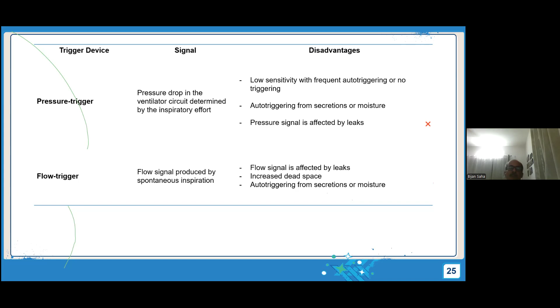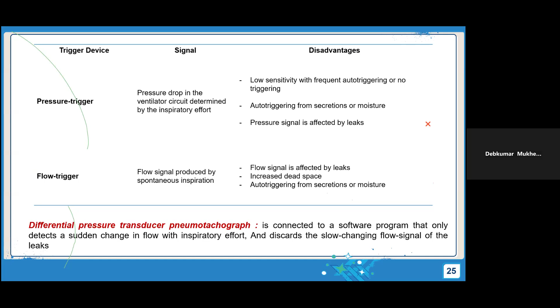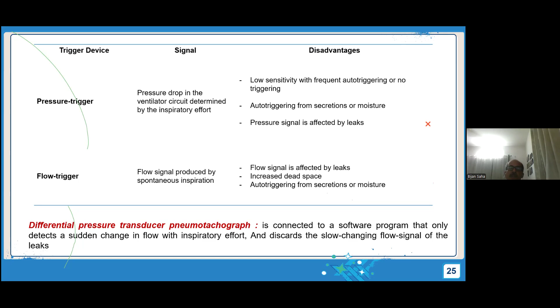So there is another flow sensor called the pneumotachograph. This is also a flow sensor, but it is not a hot-wire anemometer. Because of the change in the flow, there is some change in the pressure. That change in the pressure will be detected by the machine, and the machine will then deliver a breath. And the ventilator discards the slow-changing flow signal of the leak. Some ventilators use the pneumotachograph. Even with the pneumotachograph, what we have seen in our clinical practice is that the patient has to generate a good amount of flow; otherwise the patient will not be able to trigger a breath. That is why the bigger infants may trigger a breath, but the smallest infants will not be able to trigger a breath. Next slide, please.